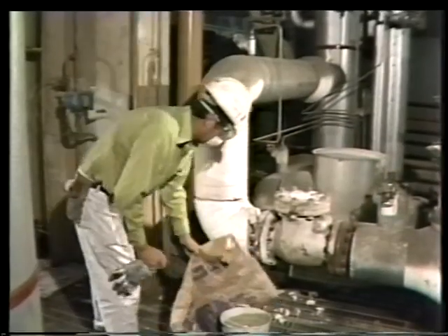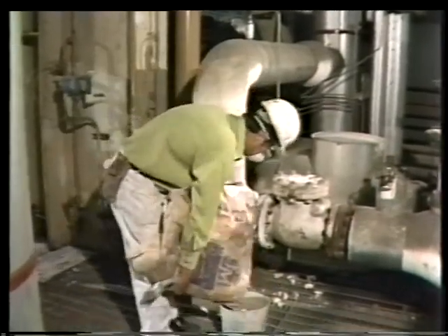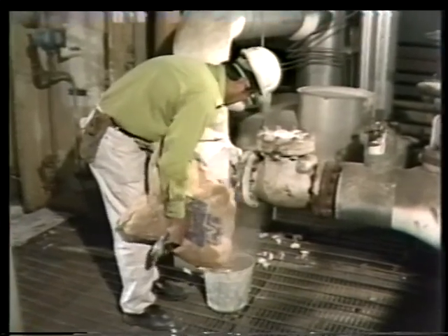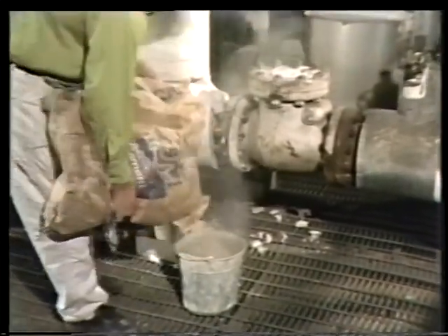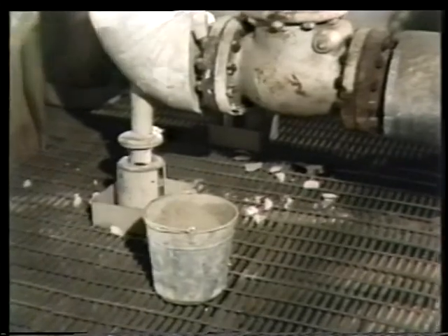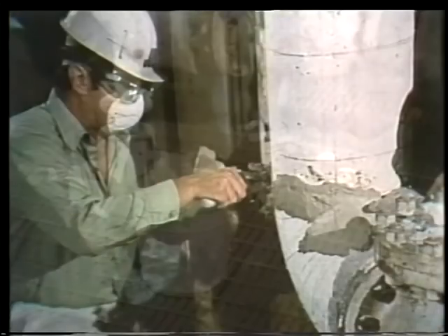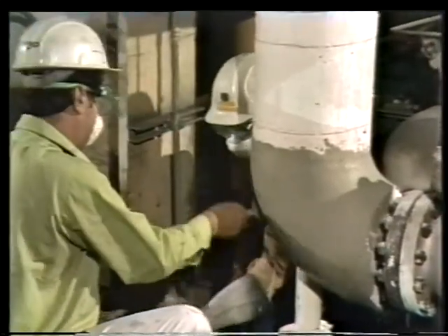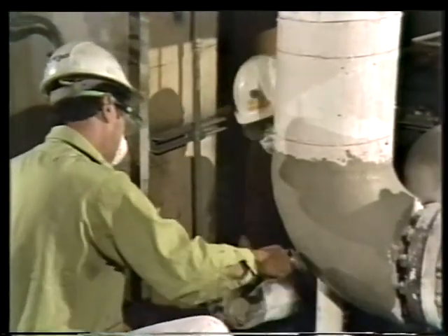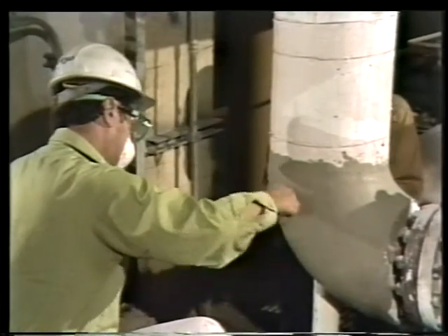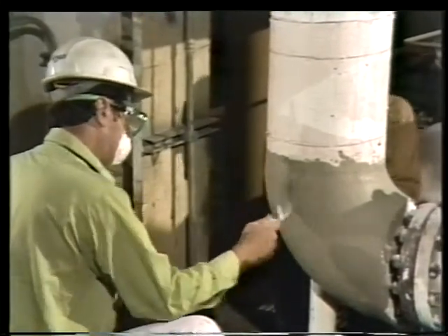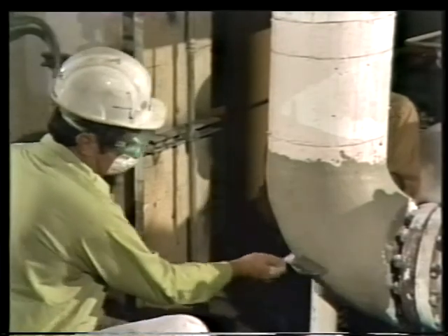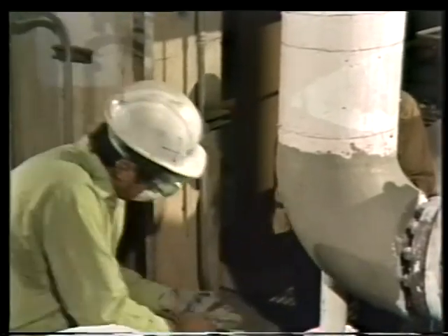Insulating cement is used to fill the remaining cracks. The mud is usually mixed up by hand on the spot in the exact quantities needed for the job. It's troweled into the cracks to seal off possible heat leaks and smoothed over the entire elbow. With a steady hand and a good eye, it's possible to form a hard, airtight shell that makes a nicely rounded, smooth surface for lagging.